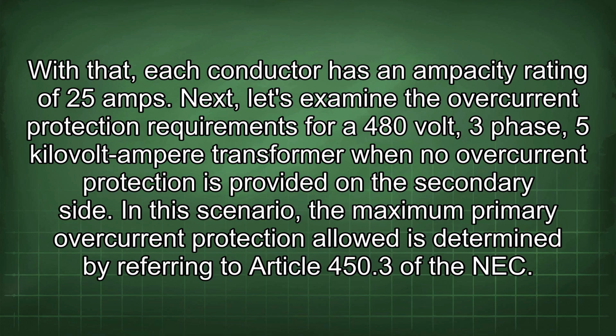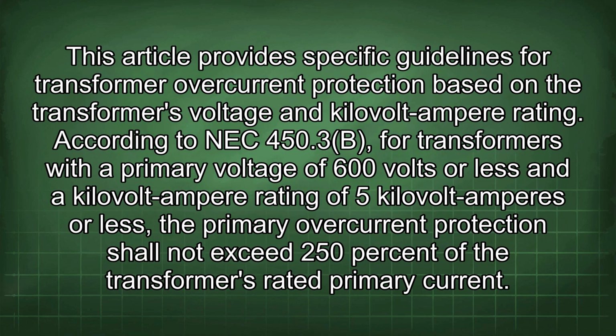Next, let's examine the overcurrent protection requirements for a 480 volt, 3-phase, 5 kVA transformer when no overcurrent protection is provided on the secondary side. In this scenario, the maximum primary overcurrent protection allowed is determined by referring to Article 450.3 of the NEC. This article provides specific guidelines for transformer overcurrent protection based on the transformer's voltage and kilovolt ampere rating. According to NEC 450.3(B), for transformers with a primary voltage of 600 volts or less and a kilovolt ampere rating of 5 kilovolt amperes or less, the primary overcurrent protection shall not exceed 250% of the transformer's rated primary current.